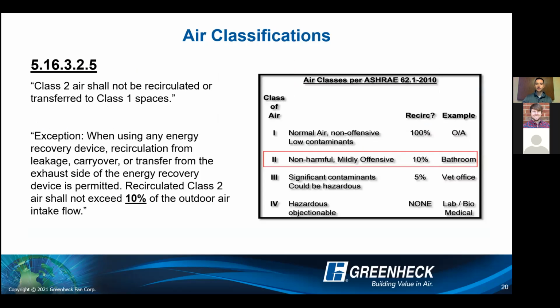But one thing I want to touch on before you utilize a purge or request a purge is the different air classifications and whether or not energy recovery can be used. And so looking at the different classes of air per ASHRAE 62.1, you can see there are 4. First one is going to be office spaces where you're likely sitting at right now, or potentially, residential type applications where you have very normal air. It's not offensive, low contaminants, 100% recirculation is allowed. Really doesn't matter about cross contamination because it's coming from a clean space.